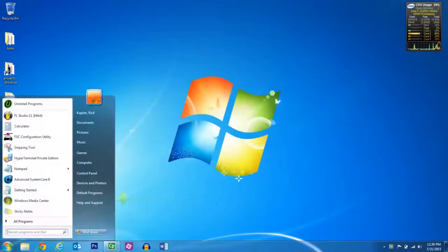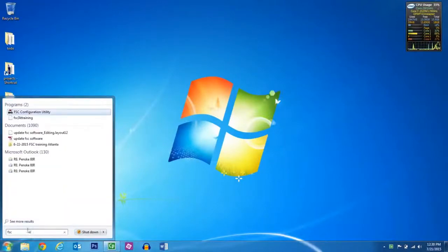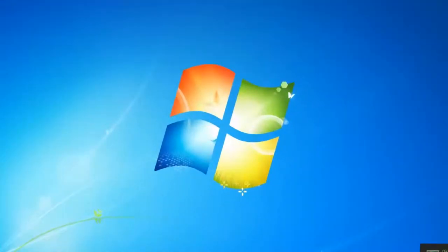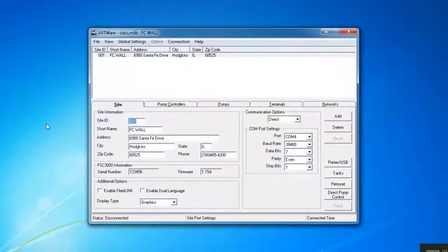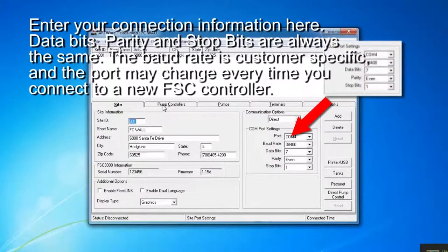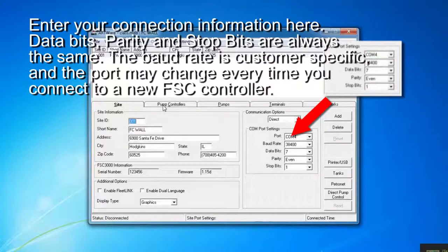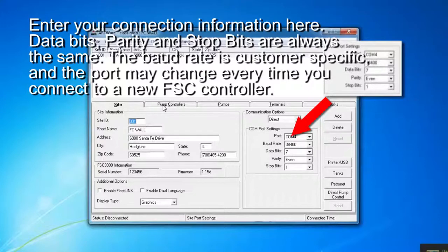Then we need to open up the FSC configuration utility, also known as Artware. Enter your connection information here. Databits, parity, and stop bits are always the same. The baud rate is customer specific and the port may change every time you connect to a new FSC controller.